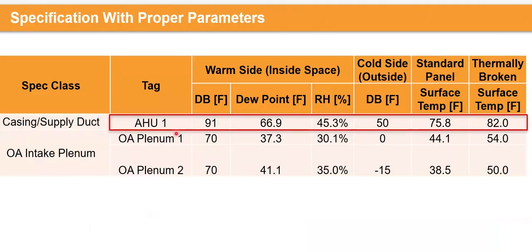For a standard supply duct, you do have your warm side around 91, that's heated warm air. And you do have your cold side around 50. This is typical as we see it. Your dew point would be at 66.9. Well, the standard panel would have a surface temperature of 75, which is above that, so there'll be no condensation. Thermally broken obviously would be a superior product with a much higher surface temperature.